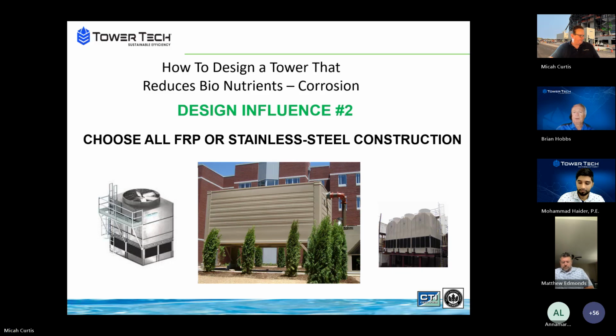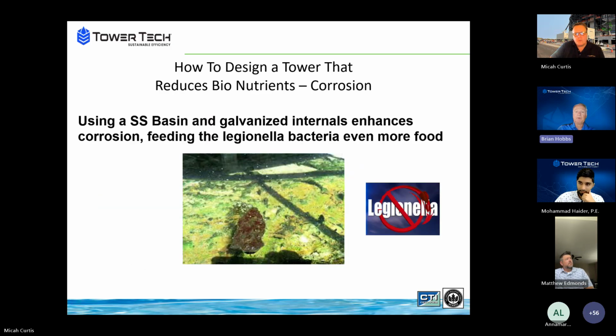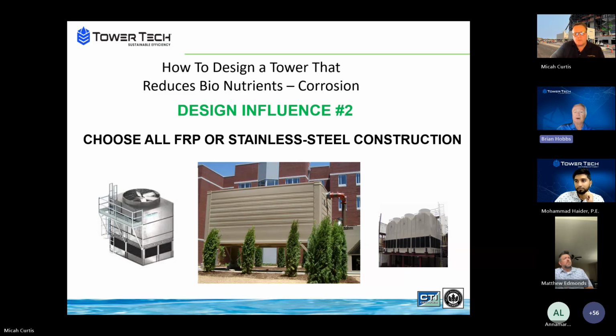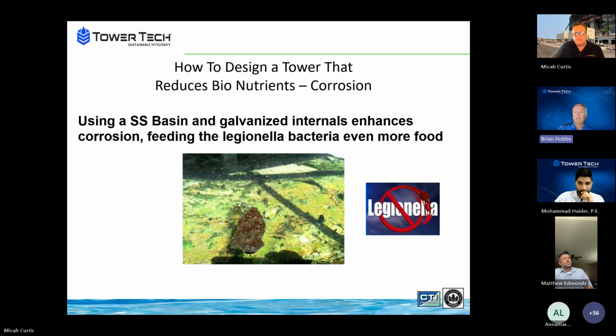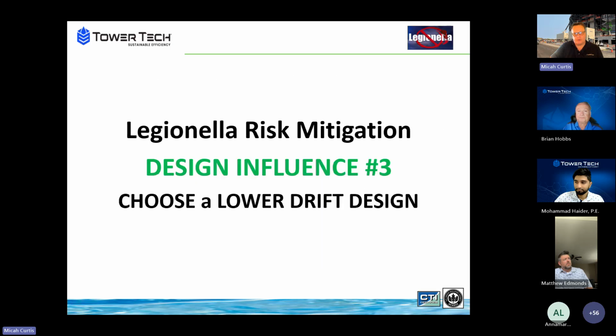And what about FRP? FRP, we see here and there a lot of specs that do spec out FRP or some other type of material, as long as it's not corrosive. And those aren't as many as we see in the galvanized or the hybrids out there, the non-corrosive units. Correct. So, to repeat what we talked about earlier, if you get rid of algae and corrosion, you've eliminated the two food sources that Legionella bacteria thrive off of. So that's a big deal, choosing a non-corrosive cooling tower.